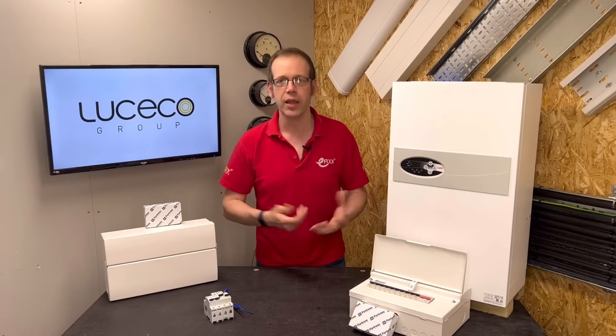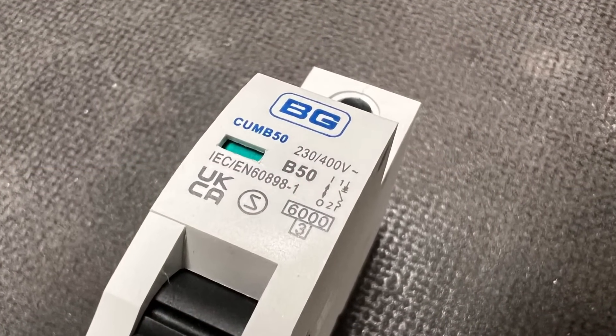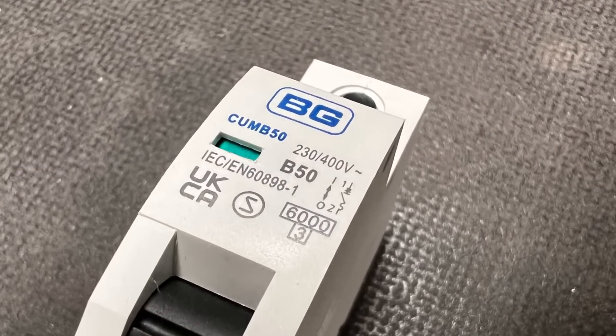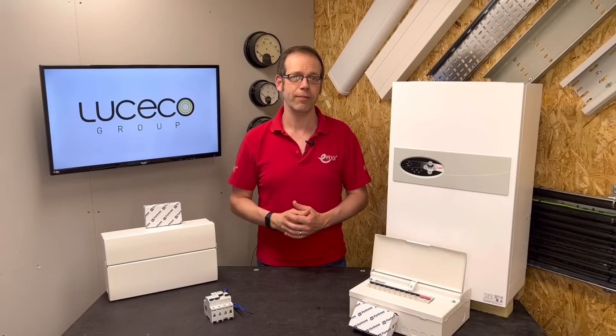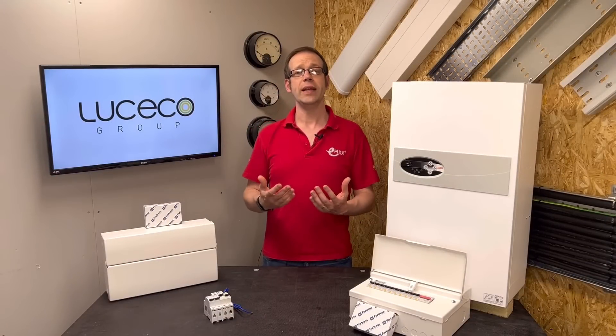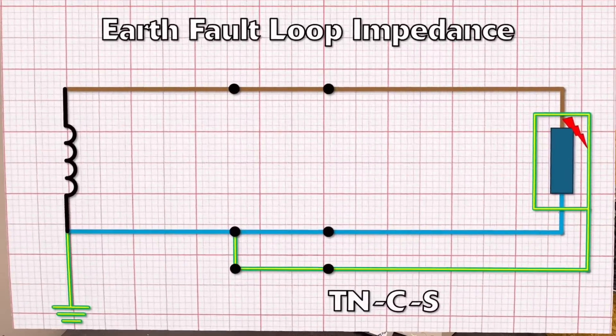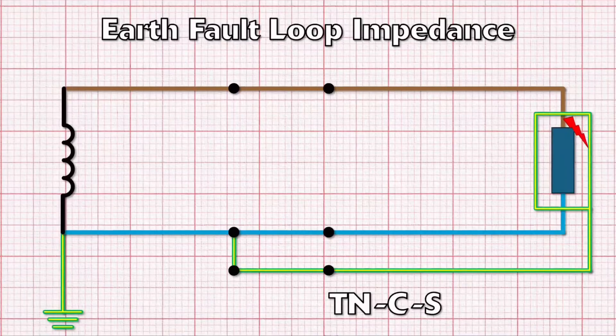Electrical design is fun! We want a low earth fault loop impedance in order to cause a high current flow to operate the protective device quickly — that's the basic principle. To achieve this we need to figure out the highest earth fault loop impedance of the circuit, because that is the worst-case scenario. This will be found at the point with the greatest length of conductors from the protective device.